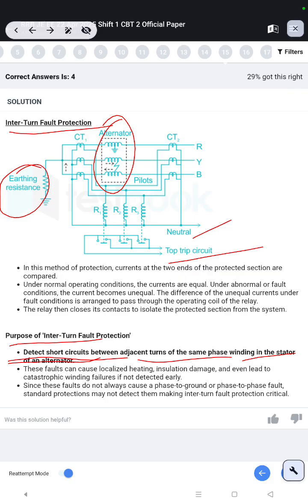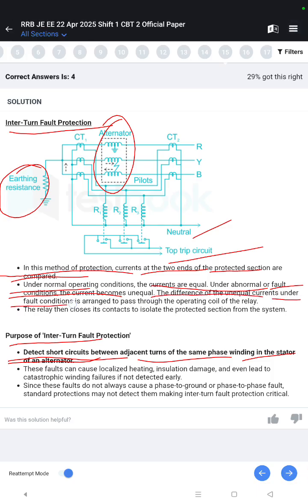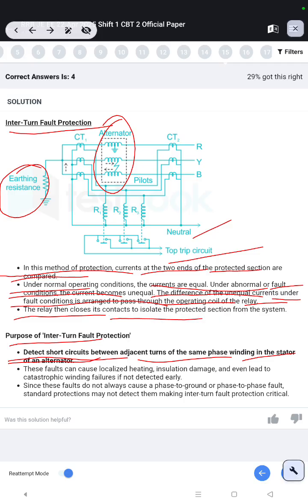In this method of protection, the currents at the two ends of the protected section are compared. Under normal operating conditions, the currents are equal. Under abnormal or fault conditions, the currents become unequal. The difference of the unequal currents under fault condition is arranged to pass through the operating coil of the relay. The relay then closes its contact to isolate the protected section from the system.